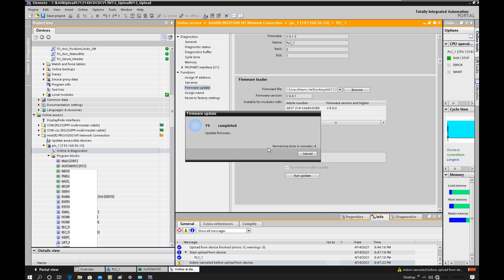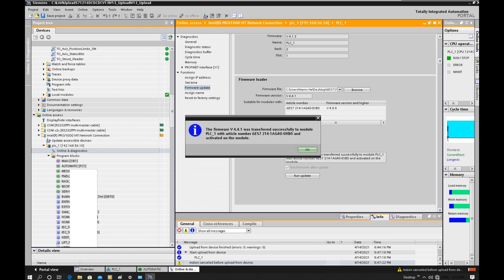This update might take a couple of minutes. Meanwhile, your CPU will shift to stop mode and the maintenance LED will show a yellow indicator. The firmware version 4.4 was transferred and upgraded successfully. Click OK.